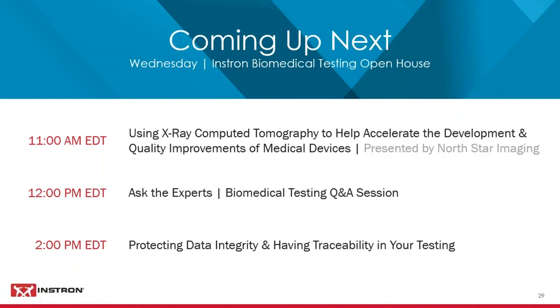So the next question is, which calculations are validated in the calculation suite? IQOQ validation in the standard says it should replicate the software as it's intended to be used. So the calculations that are validated should replicate those you're using in your test methods. At the time of quotation, you'll work with our sales representatives to determine which calculations best suit your needs, and those will be the ones quoted in the IQOQ document package.